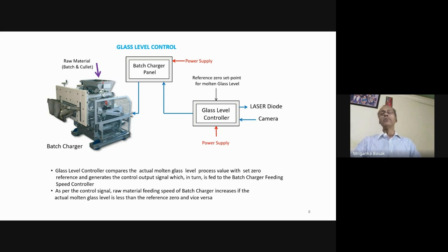In some of the machines, job change is going on. In some of the machines, the mold change is going on. In some of the machines, the section is stopped because of some breakdown. So that is basically a disturbed situation. This is noise, in fact. We cannot take the feedback from this. This is not a standard for measurement. The level has to be the standard for measurement. So although it is basically a three-element control, we are controlling the level only.